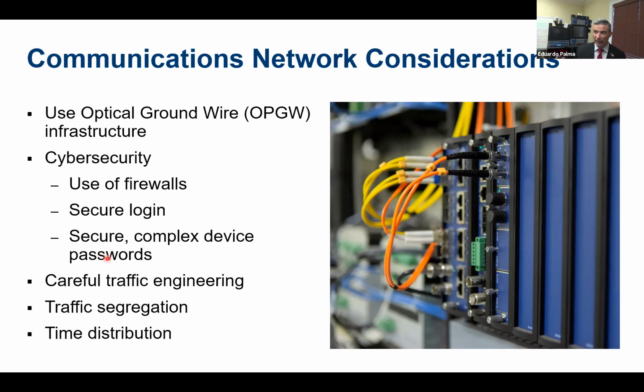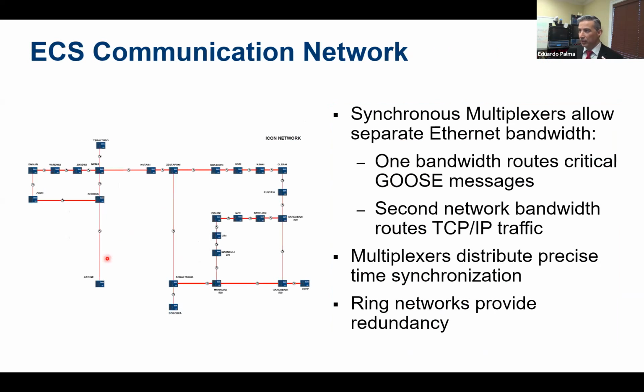The engineering of the traffic was set through these multiplexers in order to create traffic segregation, and something that was very important also, time distribution. So it is a synchronous network. The synchronous multiplexers had a bandwidth, like I said before, to route critical GOOSE messages, and a second network bandwidth through the same fiber optic cables to route TCP/IP traffic, the traffic that is updated not in milliseconds, but in half a second or a second.